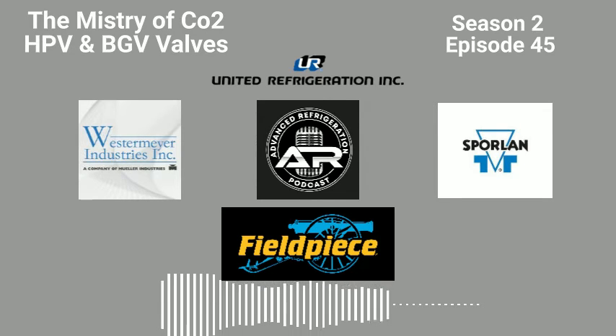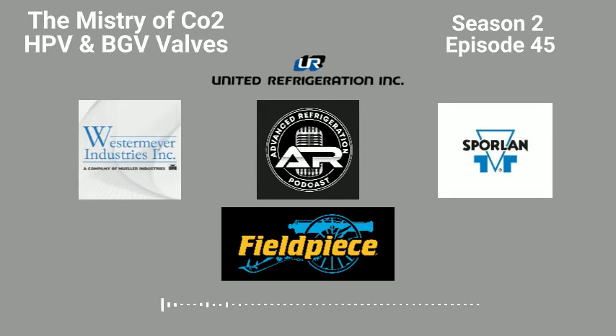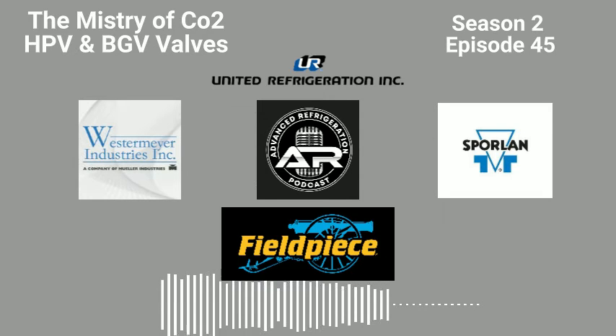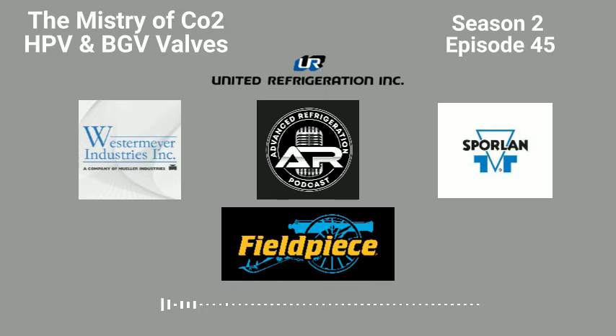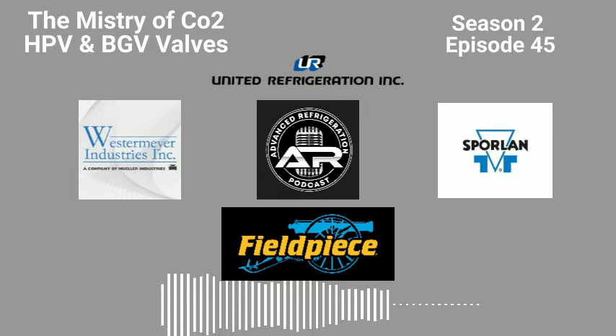I've seen them 100 feet away, and I've seen them work fine. Really? Yes. All the Costcos and all the Targets are at the rack, not at the condenser. See, all the ones that I've seen have been on the roof, so the condenser and the racks are right next to each other. So it's right on the outlet, the sensors and the pressure transducers. The pressure transducer is always at the valve, and the valve's always at the rack. Gotcha.